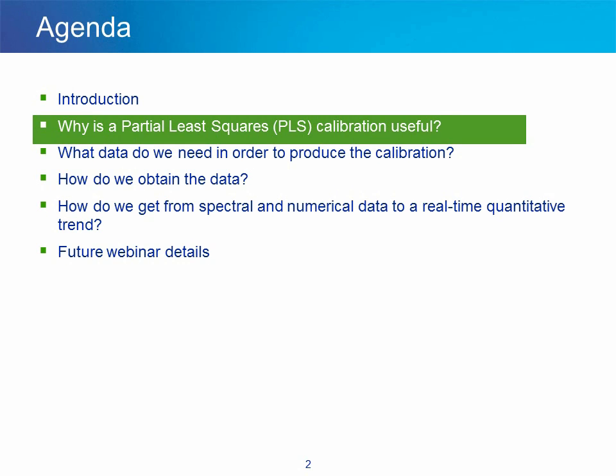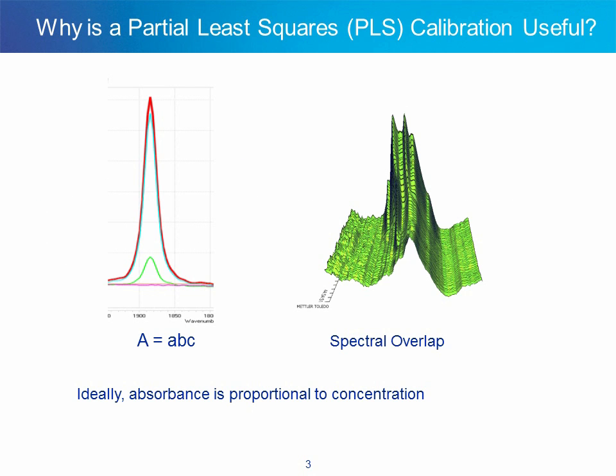Why is a partial least squares calibration useful? In many cases, a concentration of interest can be trended directly from a single peak, or perhaps a peak referenced to a baseline point. On the other hand, there are chemical and biological systems where absorbance information regarding component concentrations or physical properties of interest are overlapped and not accessible via direct absorbance trending. In cases where a univariate trend or even a ratio of trends cannot describe the concentration profile, multivariate algorithms such as PLS are very useful.